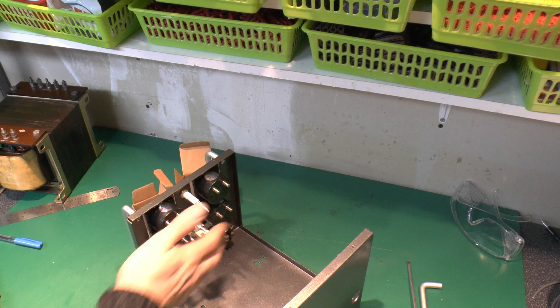Now the next thing is going to be to do all the wiring on the front here, and of course we need to do that before the transformer goes in, because the transformer, as you see where the holes are on the base, will actually come up to virtually the back of all of this, so we need to do all this wiring here first, and then the transformer goes in, and then the wires go on the top to connect to the various terminals.